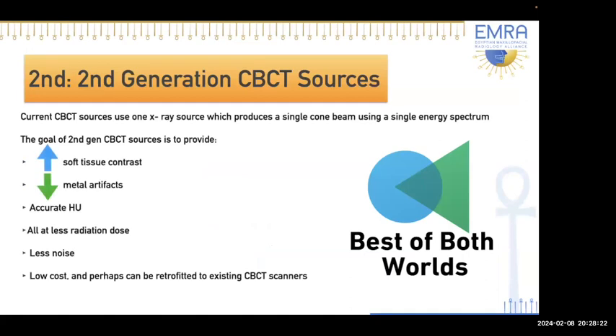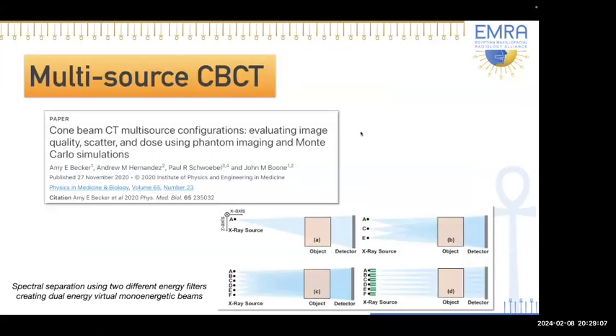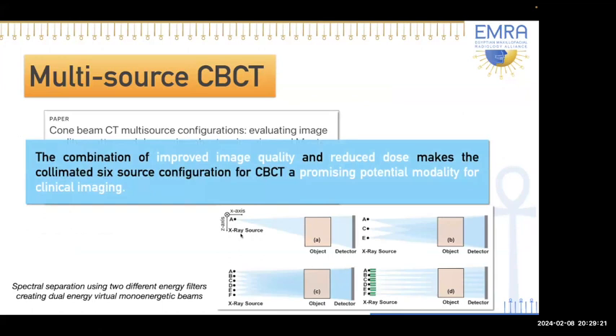Let's move on to the second technology: second-generation CBCT sources. Just as medical CT underwent multiple generations of advances, we expect the same for CBCT. The goal is to increase soft tissue contrast, decrease metal artifacts, provide accurate Hounsfield unit measurements at less radiation dose with less noise, all at lower cost — and hopefully retrofittable to existing CBCT scanners. There is substantial research in multi-source CBCT configurations that allow better image quality and reduced dose, including a six-source configuration.